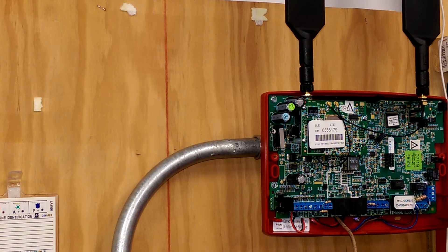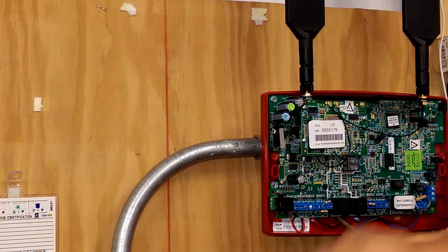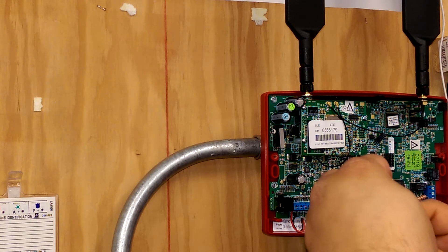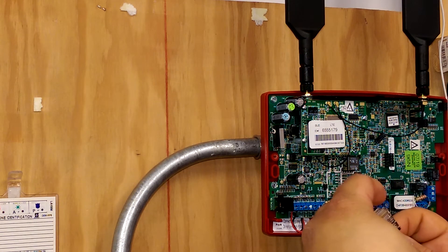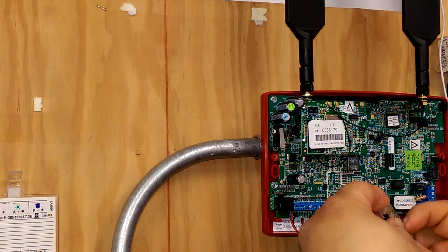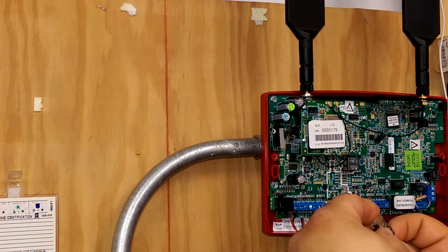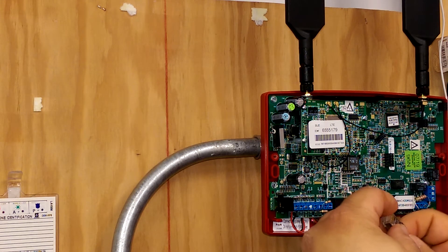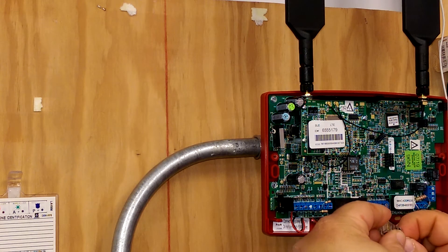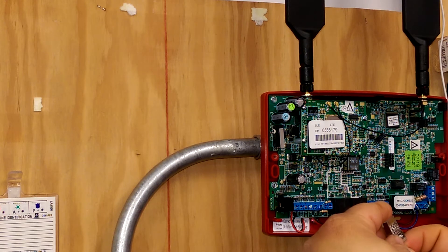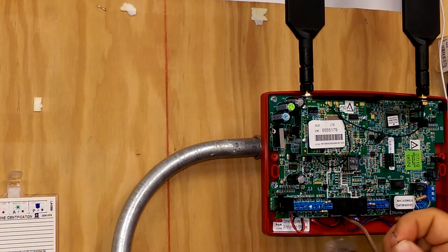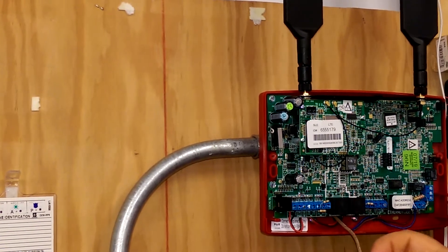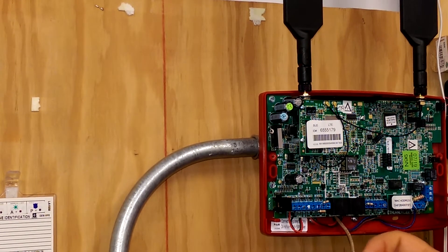And then we're just going to repeat that process with our second pair. Now this is only necessary if your fire alarm control panel has two telco jacks, which most fire panels do, but some can be turned off in order to take away the supervision. I'm going to have to make a little trim. Get them even.